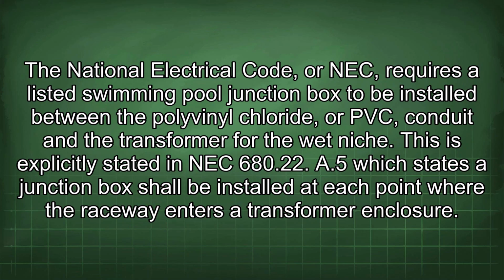The National Electrical Code, or NEC, requires a listed swimming pool junction box to be installed between the polyvinyl chloride, or PVC, conduit and the transformer for the wet niche. This is explicitly stated in NEC 680.22(A)(5), which states a junction box shall be installed at each point where the raceway enters a transformer enclosure.